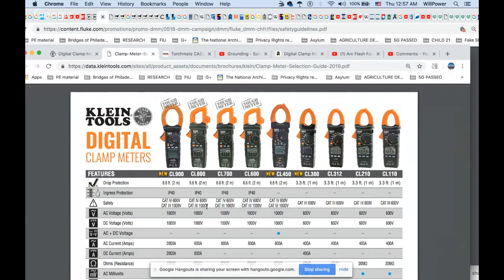But the moment you step into the Cat 4 area, I'm only going to give you 600 volts of protection. So the cats are about where you're working. So if you're working outside on the lineman on the pole above, you're not using this meter. You should be using the lineman type deal and other setups too. But this will tell you the area.